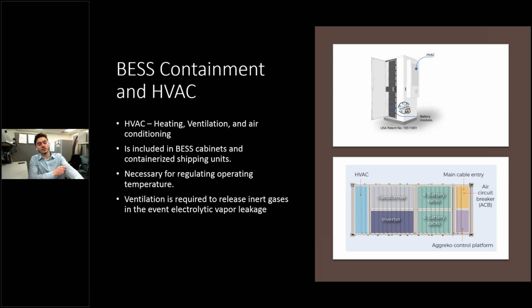Next, let's quickly touch on battery energy storage containment and HVAC. Typically, the batteries are going to be contained in a cabinet or in a storage container unit. HVAC is going to be included with these units, at least in all the cases that I've seen. And these are going to be necessary for regulating operating temperature and also necessary for ventilation, because if a battery is releasing inert gases, we cannot allow that to be contained in a unit. That has to be discharged properly.